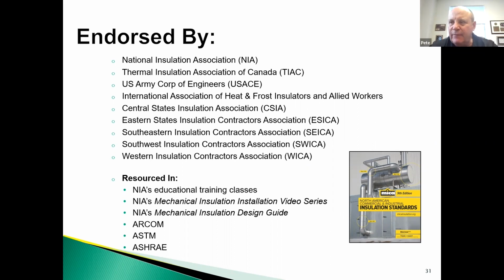Again, these are only 5 examples. If you're filling out submittals for an insulation project, you'll use piping plates for all the different systems. There are hanger plates for clevis hangers and the inserts you're supposed to use. The same with ductwork—we have duct board insulation and inserts to use with it. We also have tanks, vessels, air separators, and all kinds of equipment. All of these plates are found in the North American Commercial and Industrial Insulation Standards Manual.